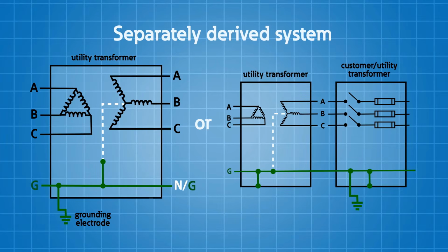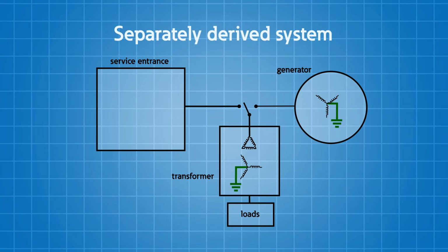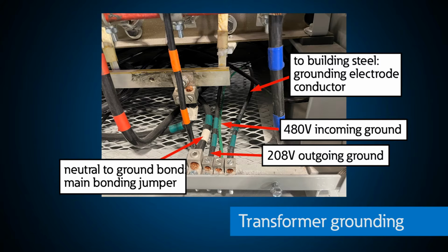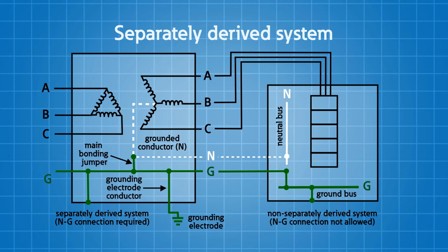Think of a separately derived system as a point downstream of the service entrance equipment where electrical isolation creates a new source. Usually, this is a new transformer connection or perhaps a generator. In either case, a new grounding and bonding scheme is required for this separately derived system. Here's an example of a separately derived system with delta Y 3-phase transformers. Here is the grounding electrode conductor, and the main bonding jumper. This establishes the grounded conductor that we talked about in the previous section.